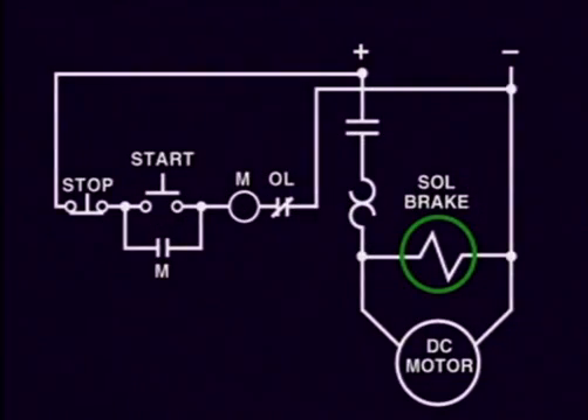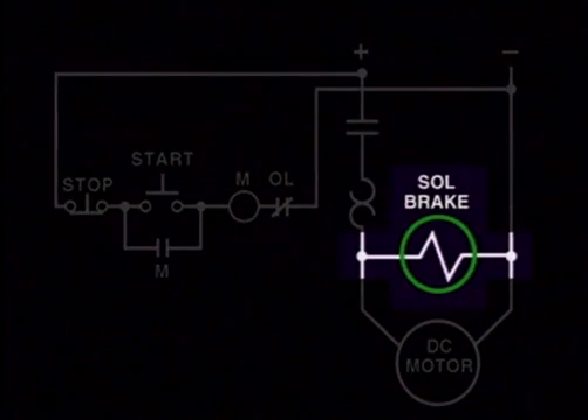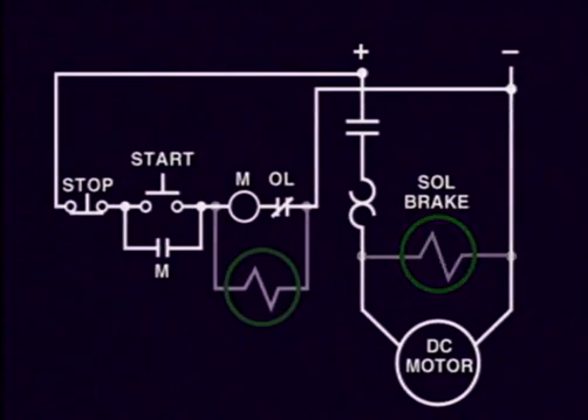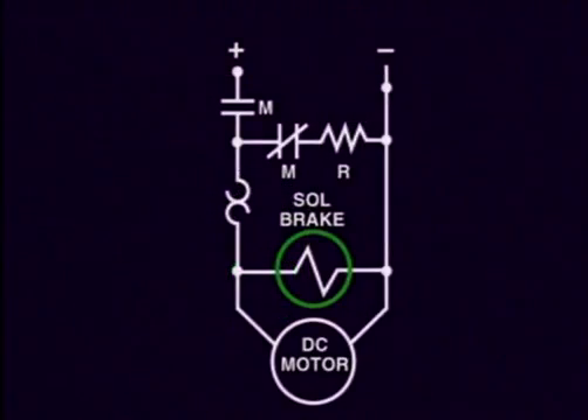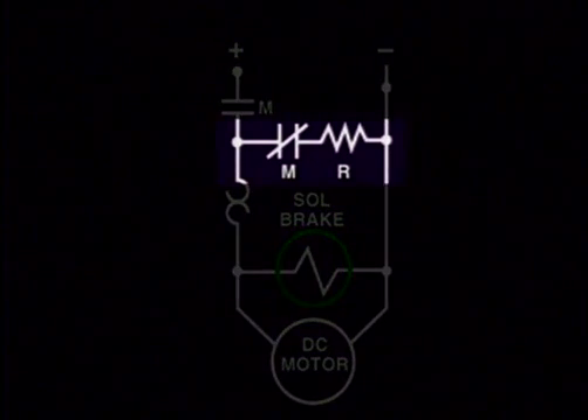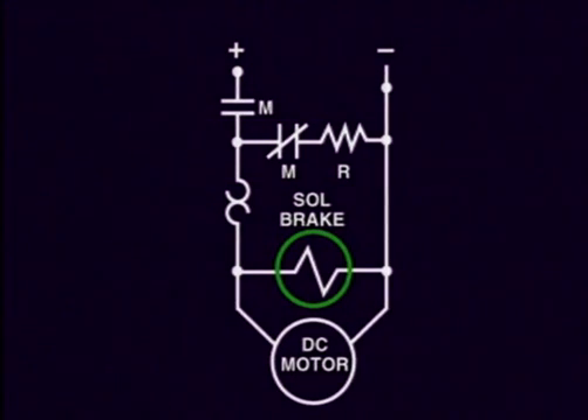The solenoid friction brake is generally connected to the motor circuit and rarely to the control circuit to avoid improper activation of the brake. As mentioned a little while ago, the friction brake could be used in conjunction with dynamic braking to hold the load in position. This allows for the brake to have a longer useful life because it can be set without maximum pressure, so the brake shoes would last longer.